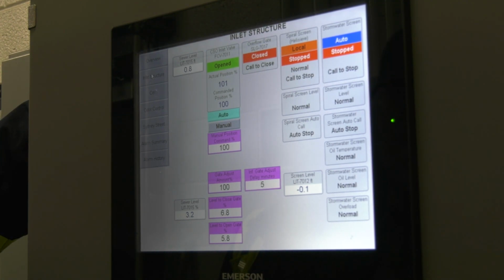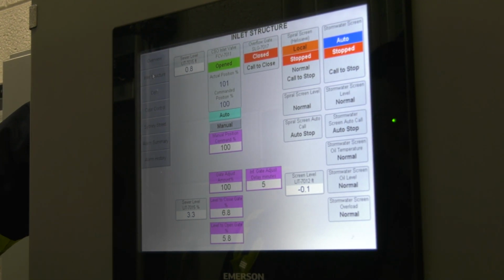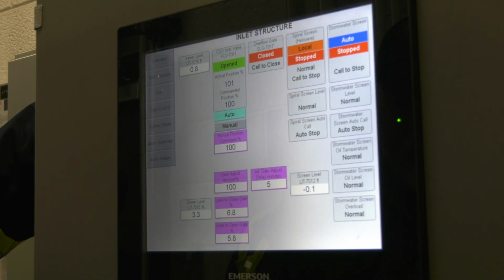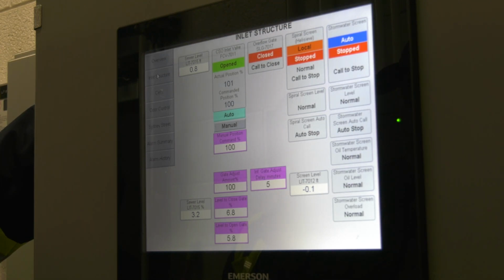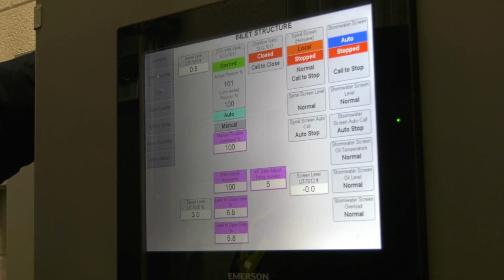Now, facility draining. You've got pumps on here, right? How many pumps do you have down there? Two pumps. Okay. The drain control is independently controlled by each cell level. So you've got 2 cells downstairs, correct? On this location. Okay. And they're low level signals. They're combined. Is that correct? Yeah. Okay. Once the level rises above 2.67 feet and then falls back below 2.67 feet, the pump will be called to run until the low level float becomes true.